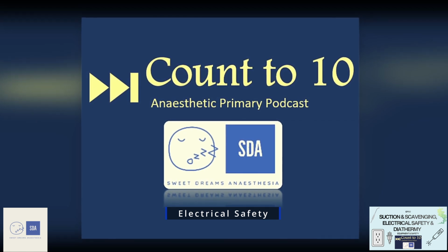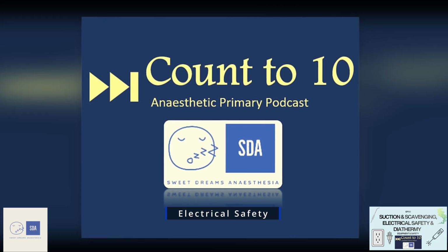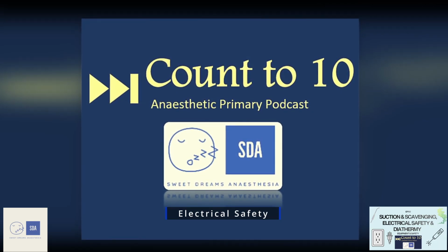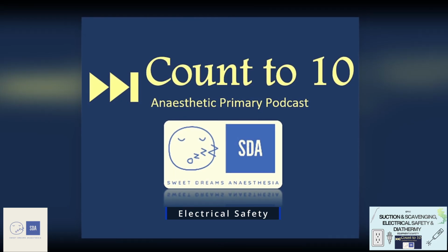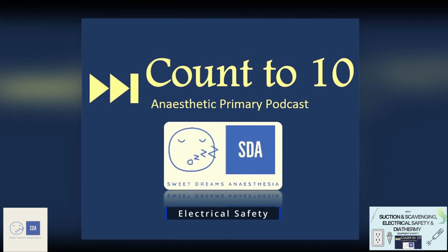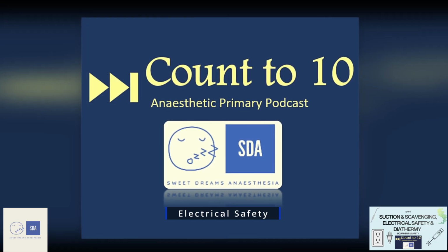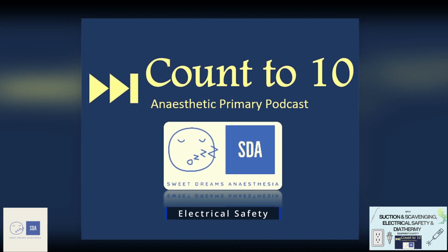Starting off with the equipment classes, there's three different types of electrical equipment classes. Class 1 refers to electrical equipment which is protected with an earth wire on the outer casing of the equipment itself. So good examples regarding this are things like refrigerators or the anaesthetic machine.